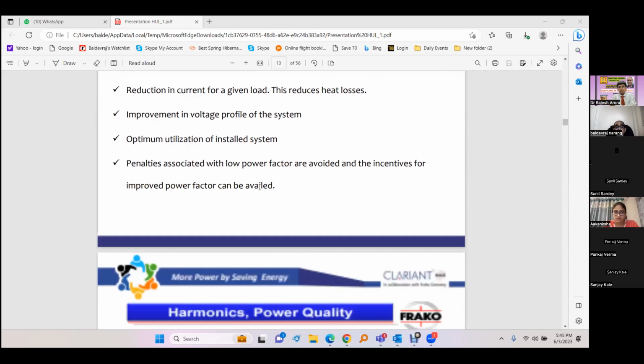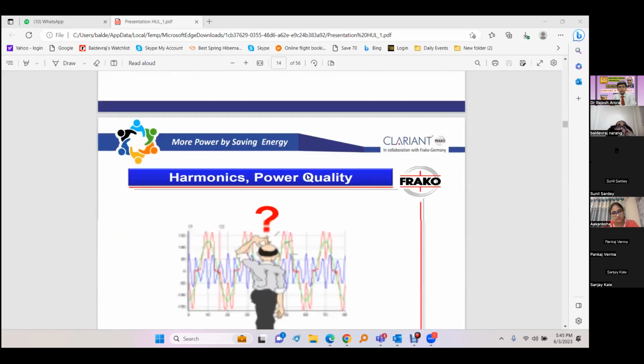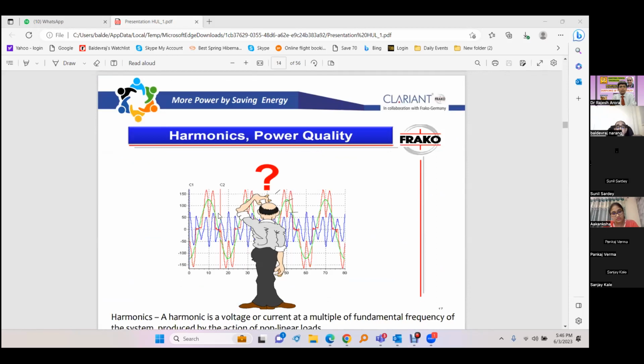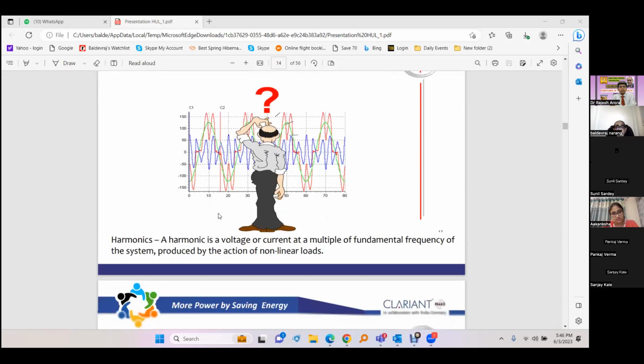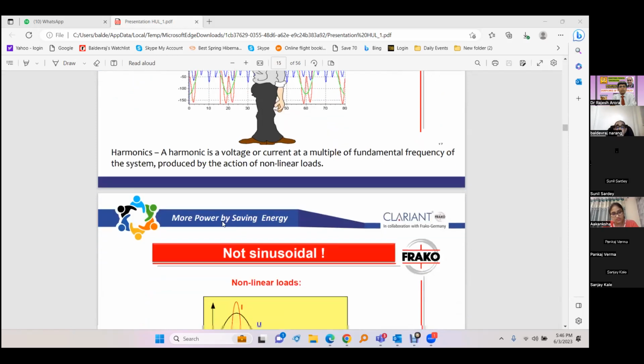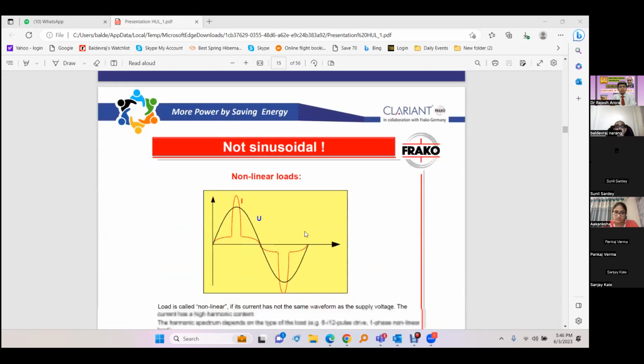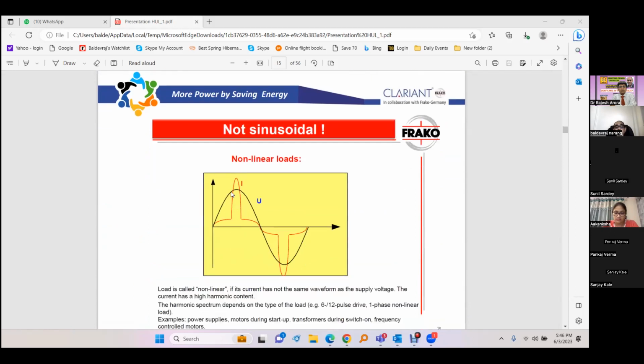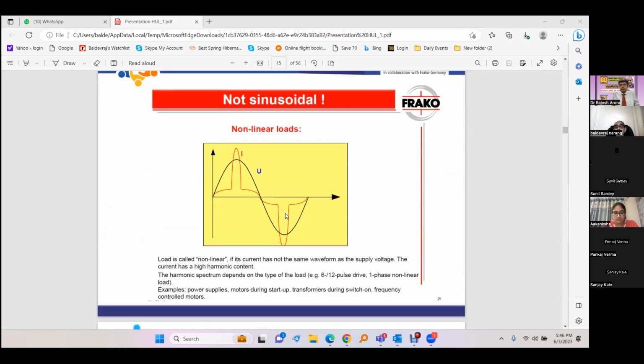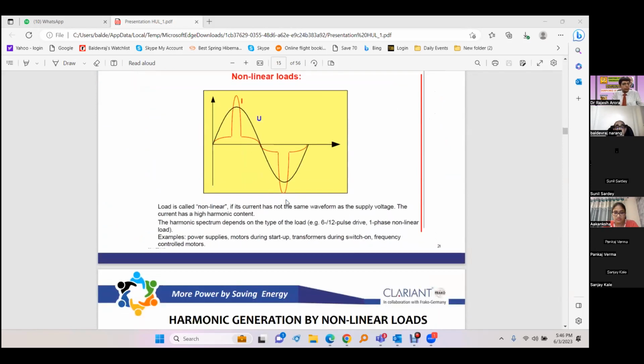So now this was the end of the reactive power. Now we have the harmonics. So we have non-linear loads and we have harmonics and then again resonance conditions which we have to take care of. Non-linear load means the voltage and current don't follow the same pattern. We apply a sinusoidal voltage, but the current does not follow the sinusoidal pattern. It has a distorted pattern because of the non-linearity. We don't use the full cycle, the full wave.